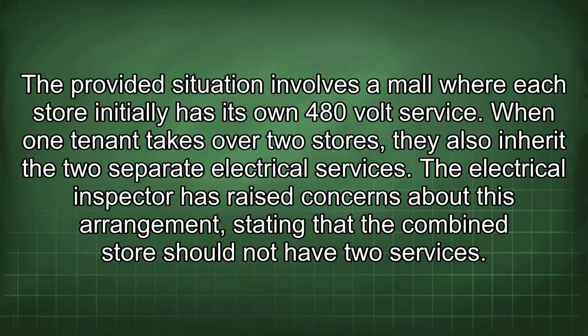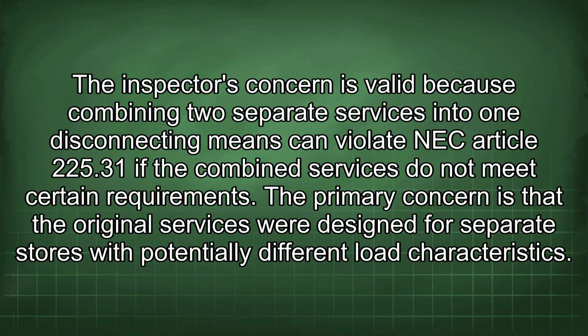The provided situation involves a mall where each store initially has its own 480 volt service. When one tenant takes over 2 stores, they also inherit the 2 separate electrical services. The electrical inspector has raised concerns about this arrangement, stating that the combined store should not have 2 services. The inspector's concern is valid because combining 2 separate services into one disconnecting means can violate NEC Article 225.31 if the combined services do not meet certain requirements.